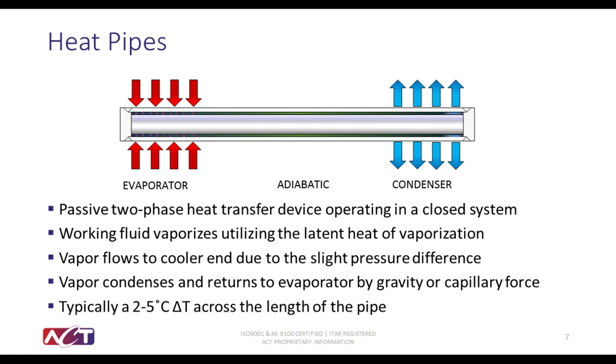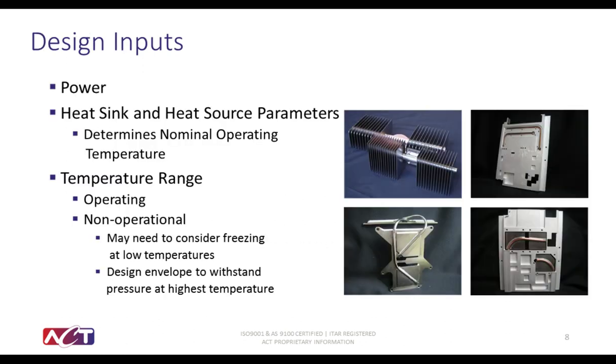What do you need to know to design a heat pipe? Well, one of the first things to consider is the amount of power that you're going to need that heat pipe to carry. The heat sink and heat source parameters are also critical to understand where that heat pipe is actually going to operate. The operating temperature of a heat pipe is one of the factors that dictates how much power it can carry. Understanding the temperature range across which you need that heat pipe to operate is also critical. If you're operating your device higher than 150, 200 C, you may need to look into a different type of heat pipe.